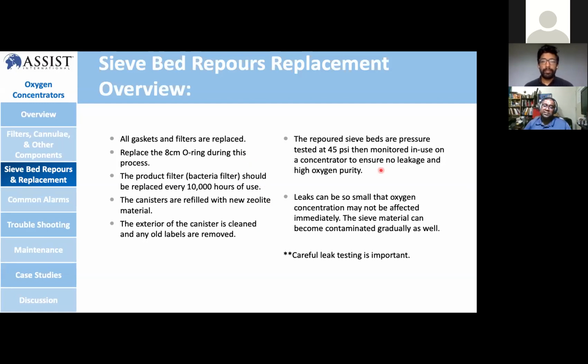And you need to do a pressure test at 45 PSI, then monitor in use on the concentrator to ensure there is no leak and the oxygen purity is high. So you need to monitor by using your oxygen concentrator. And remember, when there's a leak, the oxygen concentrator may not be affected immediately, but later on you're going to get a few unwanted issues. So make sure there's no leak when you do the 45 PSI test. The leak test is important when you complete assembling the zeolite.